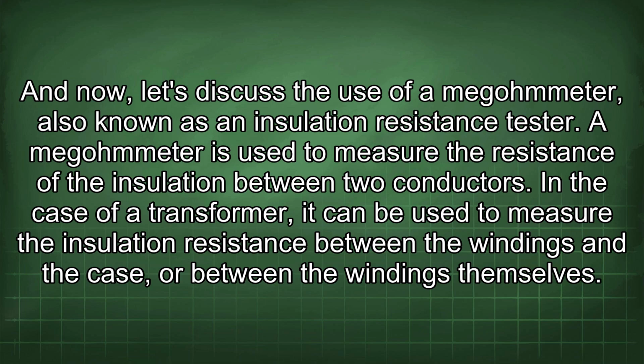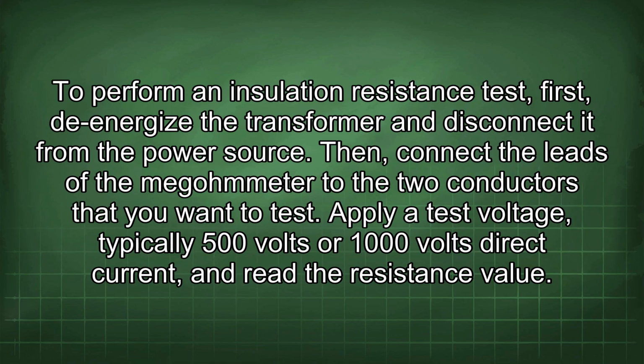A megohmmeter is used to measure the resistance of the insulation between two conductors. In the case of a transformer, it can be used to measure the insulation resistance between the windings and the case, or between the windings themselves. To perform an insulation resistance test, first de-energize the transformer and disconnect it from the power source. Then connect the leads of the megohmmeter to the two conductors that you want to test.